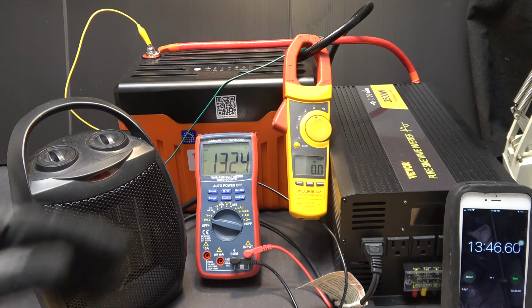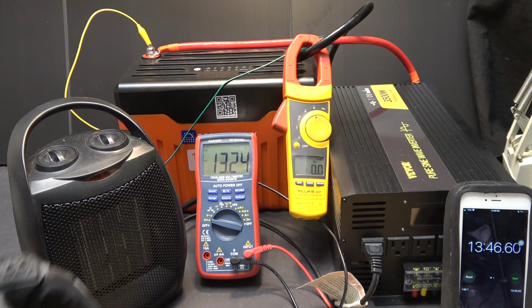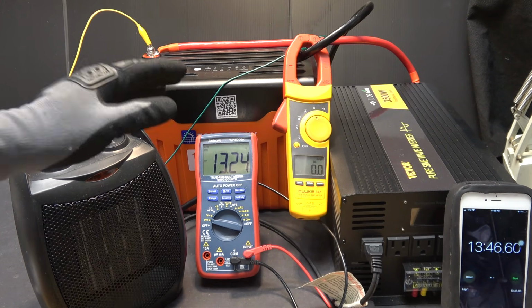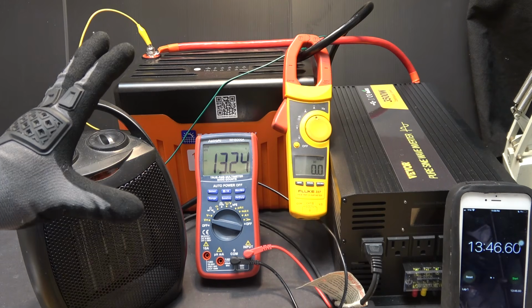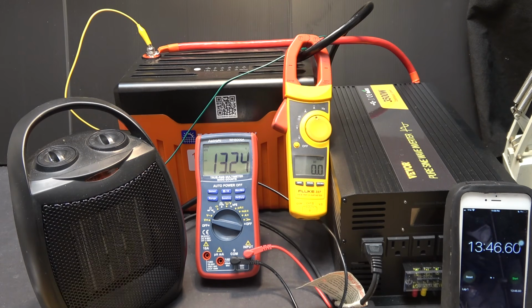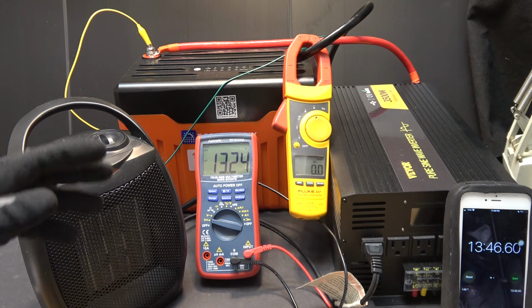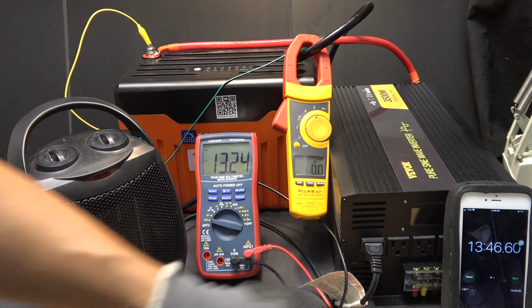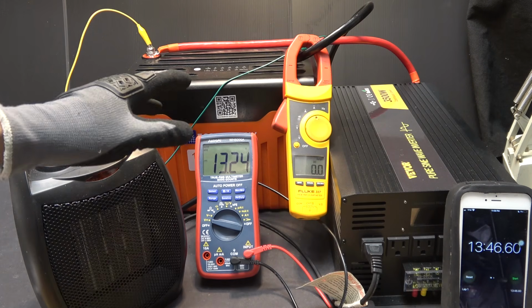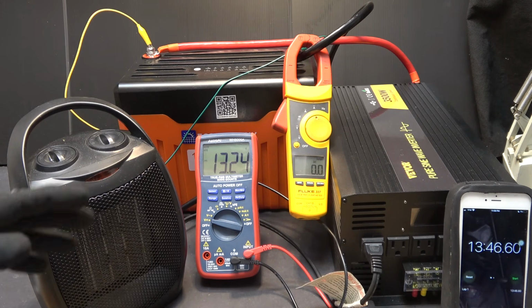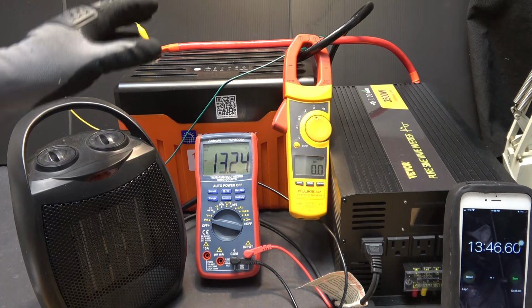So there you go. The battery runs fine when under 100 amps. When you push it over 100 amps, the BMS will shut down after about 6 or 7 seconds, and then you're going to wait a long time for it to turn back on. In this case, I waited over 13 minutes and it was still not on, so I had to use a 12 volt battery to wake up the BMS for it to turn back on.